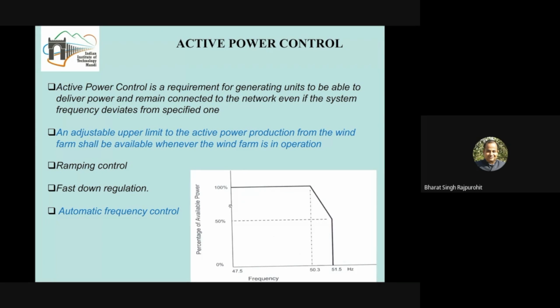Okay, so let's continue with the active power control. When we are discussing active power control, the meaning is how we will be able to control the active power of a wind farm. We are taking wind as an example. So we will be able to control the wind farm output. As I just mentioned, we have a power reference set point, and that can be changed. When the power reference set point is changed, the power electronic system changes the variable speed system so that the output can be controlled.